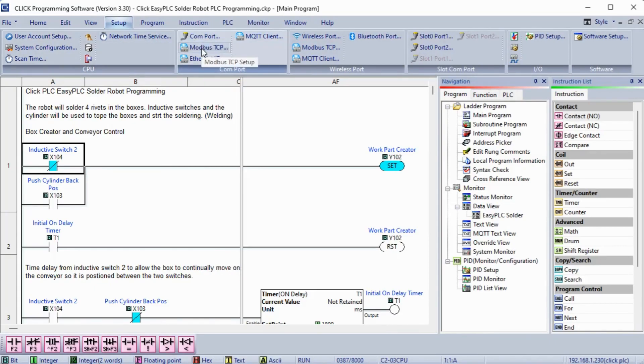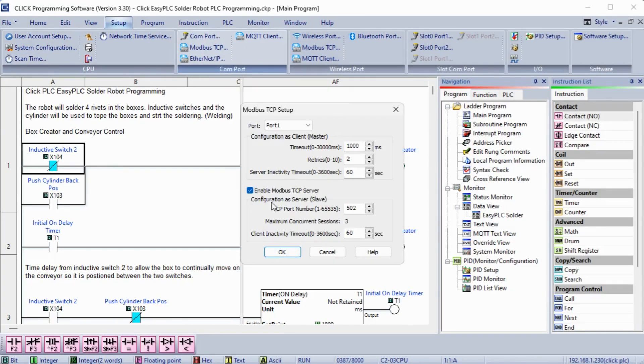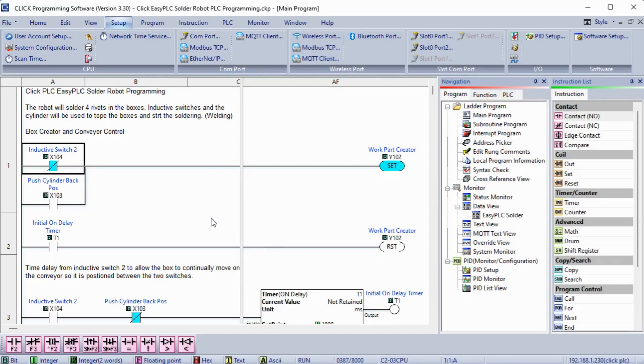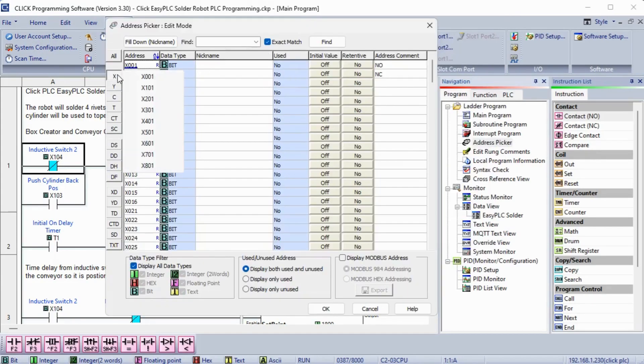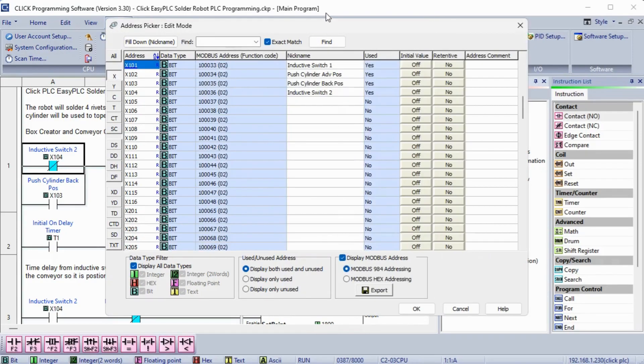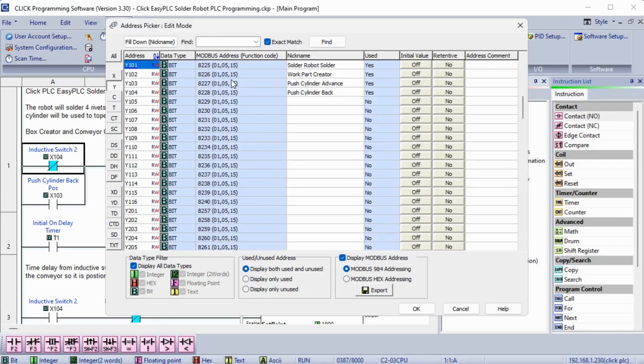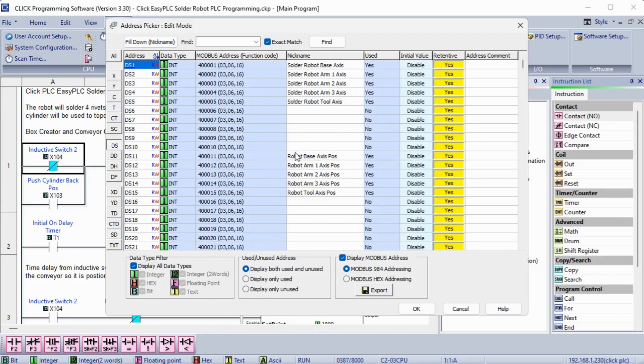The Modbus TCP Setup is located on the main menu under Setup. The enabled Modbus TCP server is selected by default. Ensure that this is chosen so that the EasyPLC Machine Simulator can communicate to the Click PLC on the default port 502. Select OK. Using the address picker, select X101. Select Display Modbus Address on the bottom right-hand side. This will show you the Modbus addresses for the inputs from the EasyPLC Machine Simulator. The output Modbus addresses can be seen by selecting Y101. DS1 to DS5 will control the robot, and DS11 to DS15 will report back the position of the robot. We will need these Modbus addresses when we test our PLC ladder logic in the next step of program development.